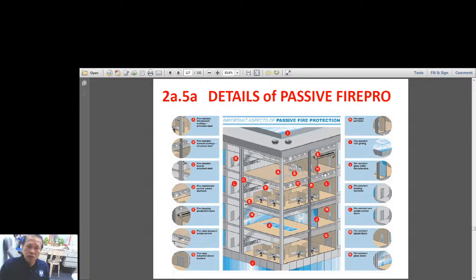the farthest sprinkler on the top, on the 50th floor, will be analyzed going down to where the fire pump is located. Whatever will be the computed pressure because of the high elevation of the building, then that will be the needed setting point of the cut-in pressure, and of course the cut-off. So as you remember, the jockey pump runs every now and then to maintain that pressure, so that on the last sprinkler at the topmost floor, it will have at least the minimum specified pressure of the NFPA, which is 7 psi.